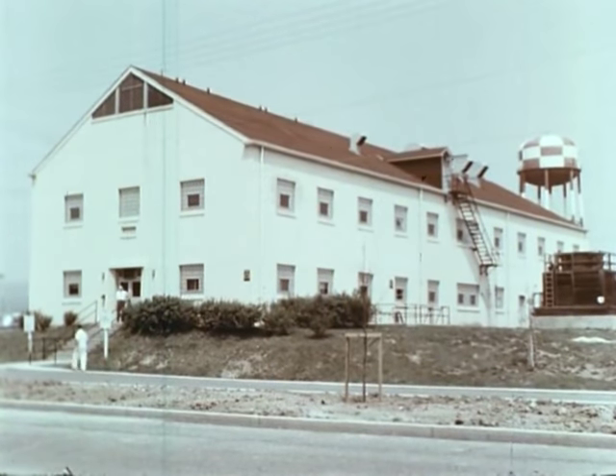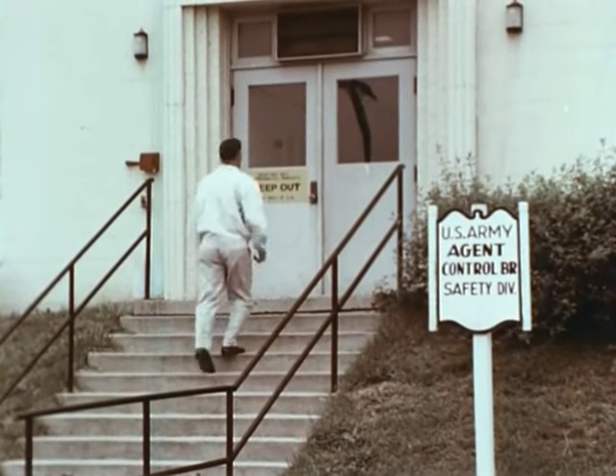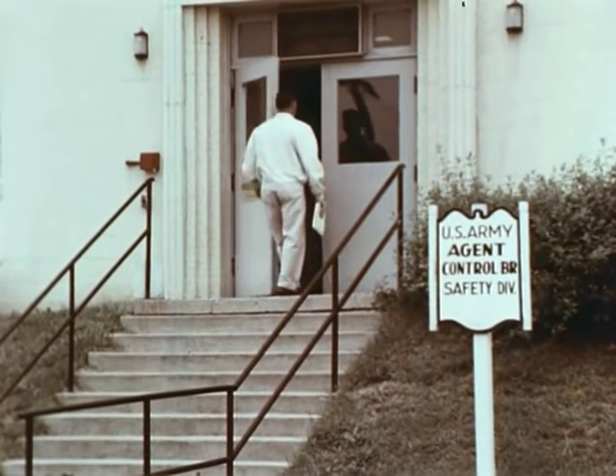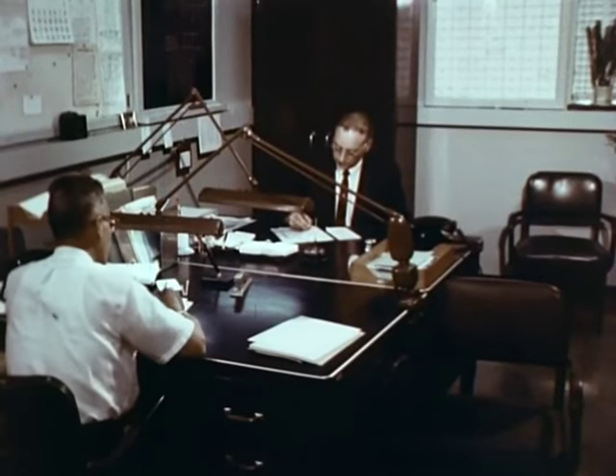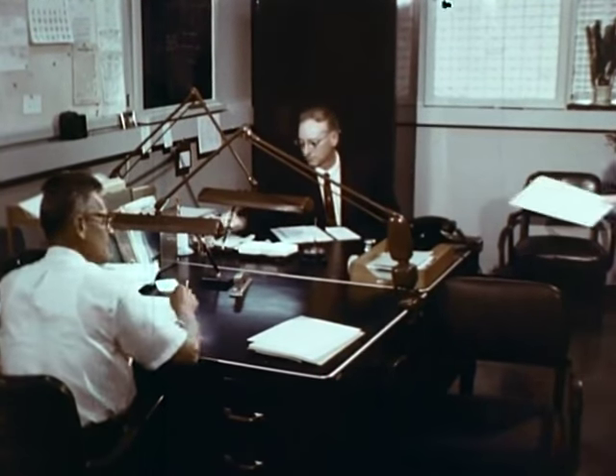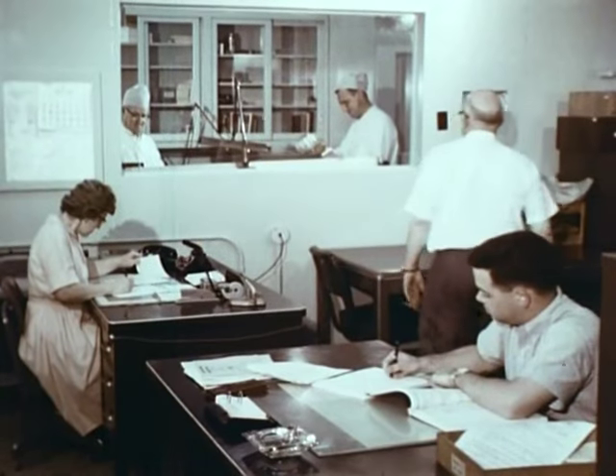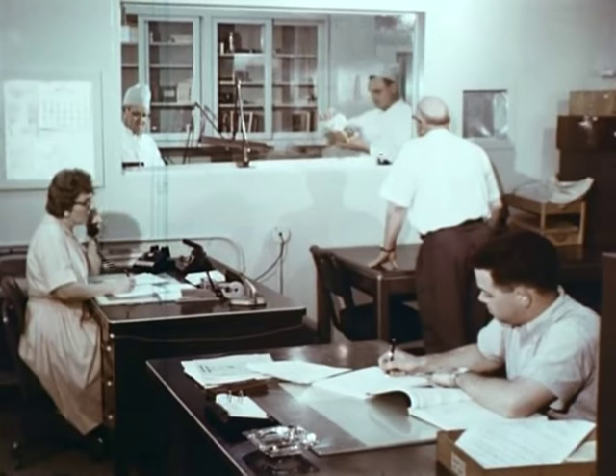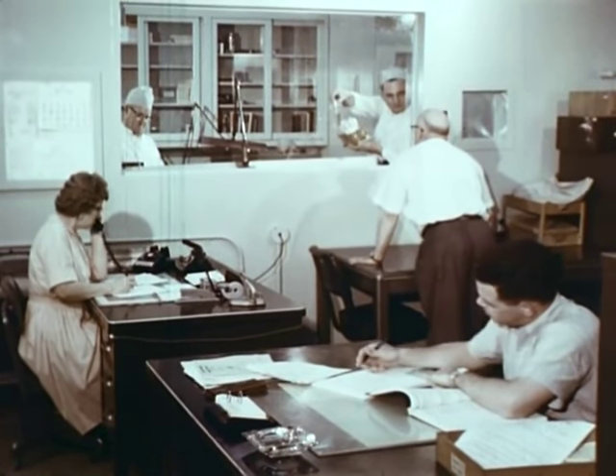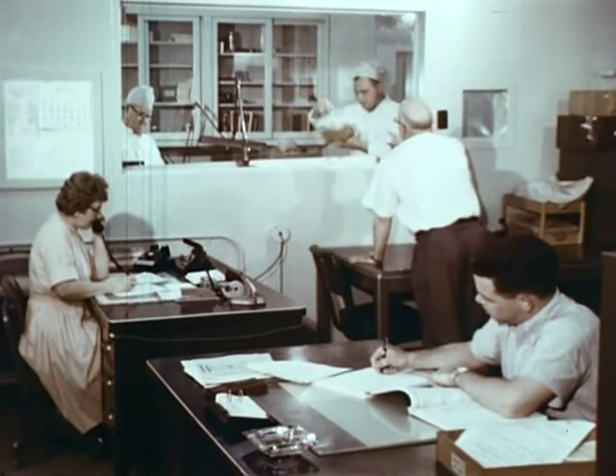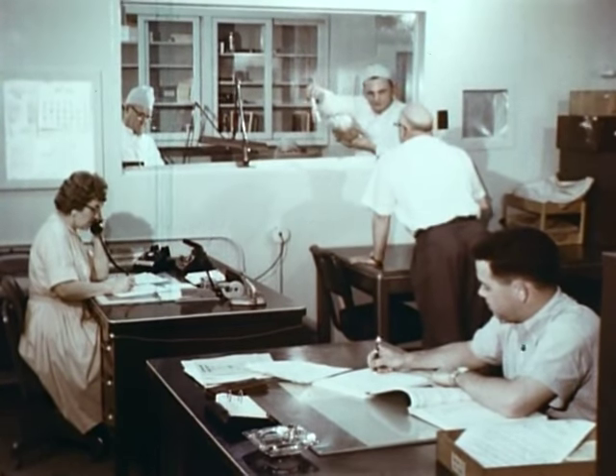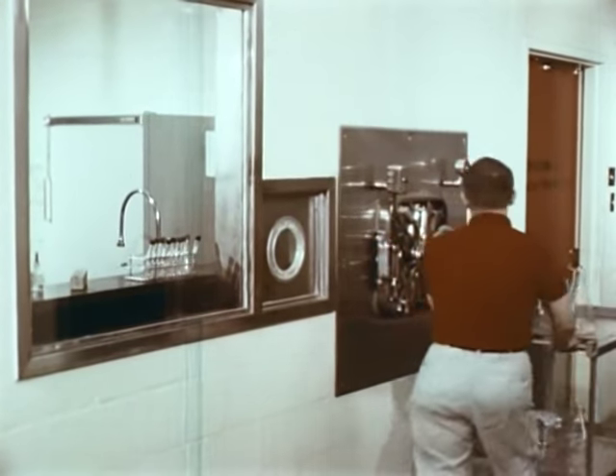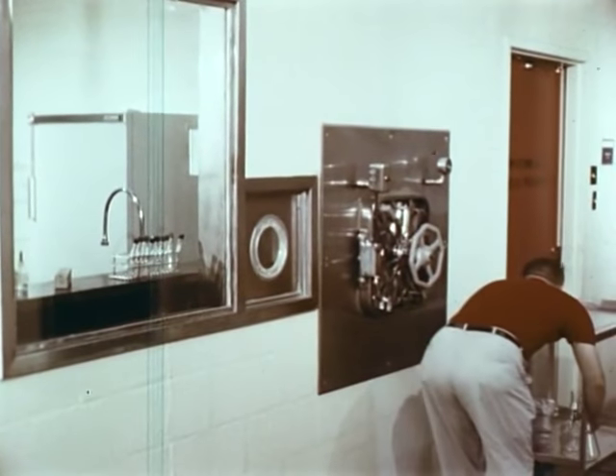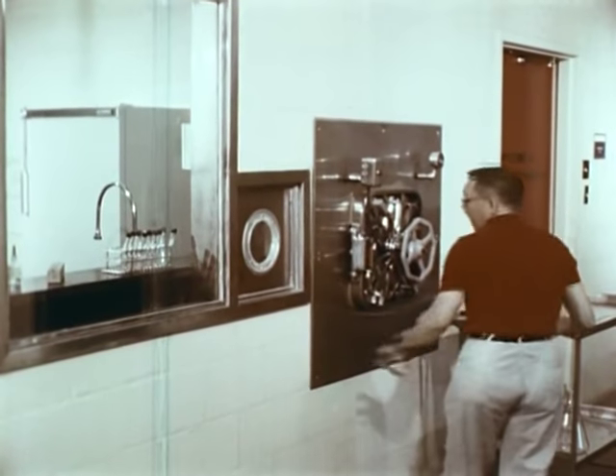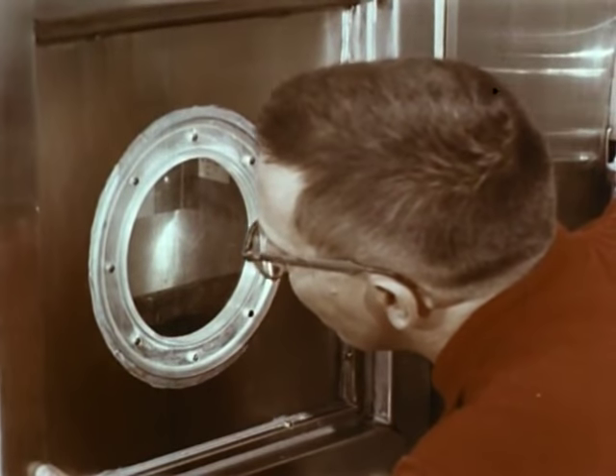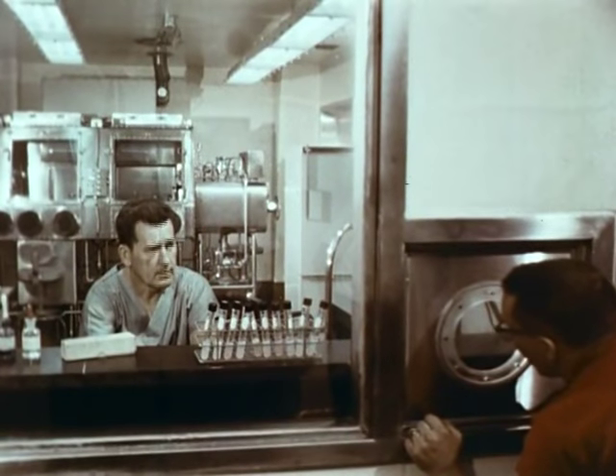Let's now observe some of the design features that one might see in the clean zone. Personnel usually enter the facility into a clean area in the front of the building, including the offices and other support areas pertinent to the operation of a laboratory. Clean offices, when located adjacent to the contaminated zone, make possible easy visual communication through a large viewing window and minimize personnel traffic between the two zones. Oral communication between the clean and infectious areas of some laboratories is often provided by means of speaking diaphragms. A tightly sealed plastic membrane provides the medium through which the sound passes.